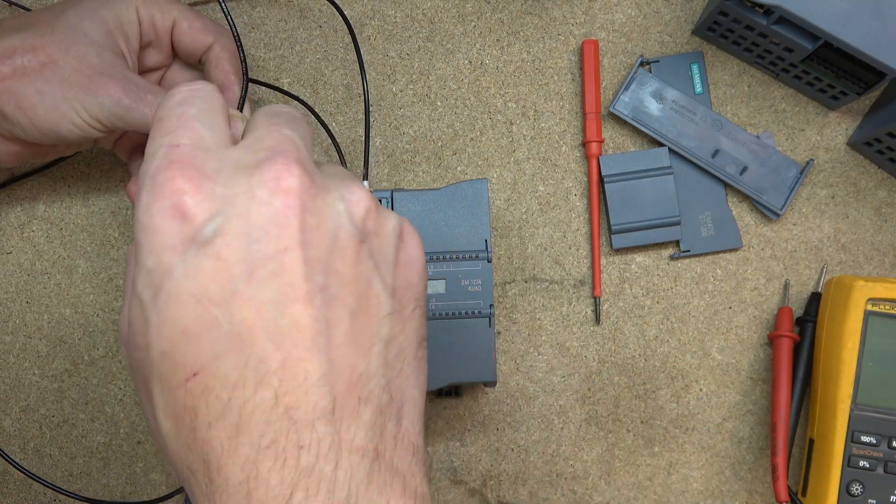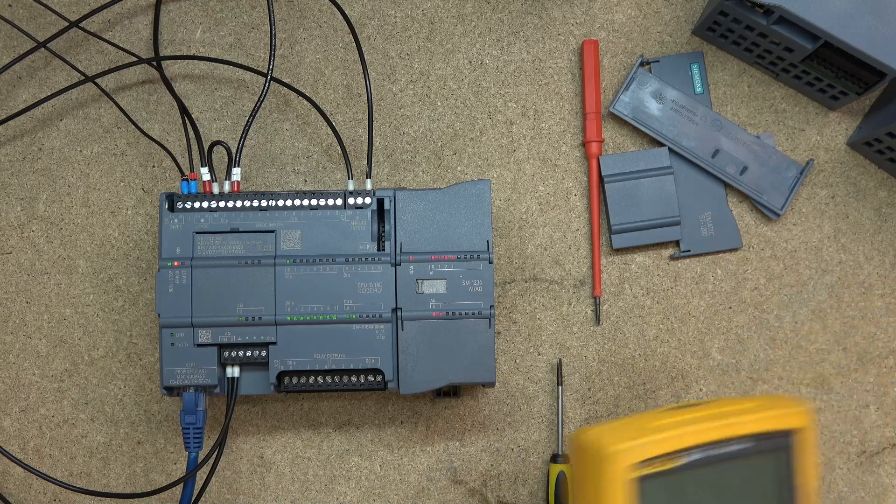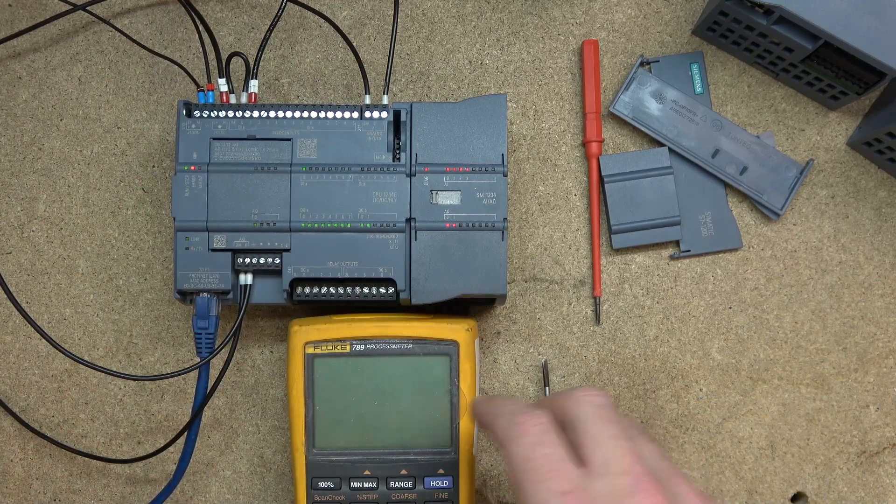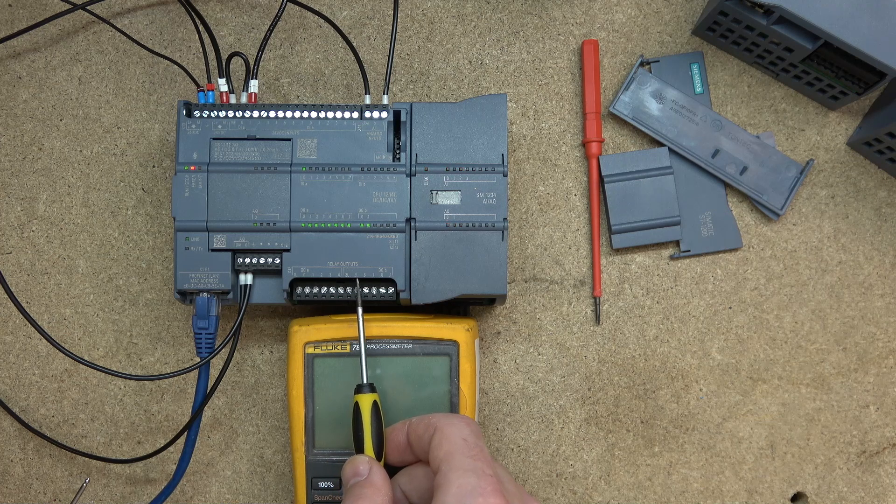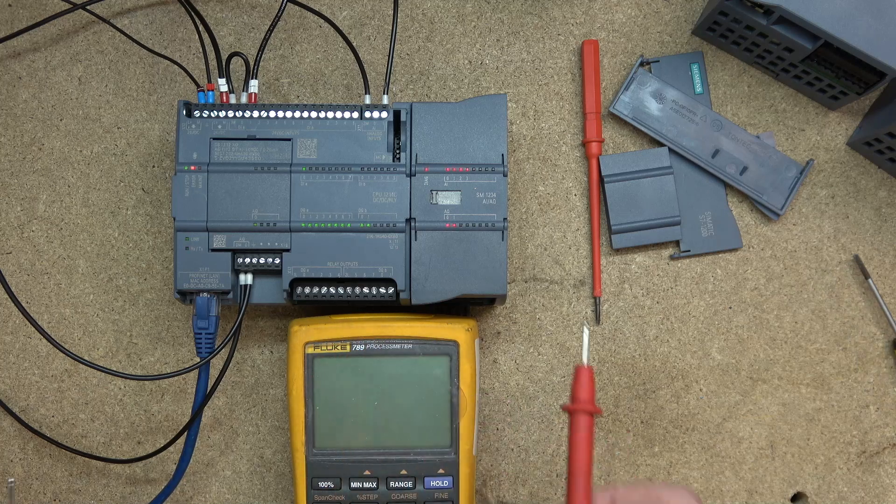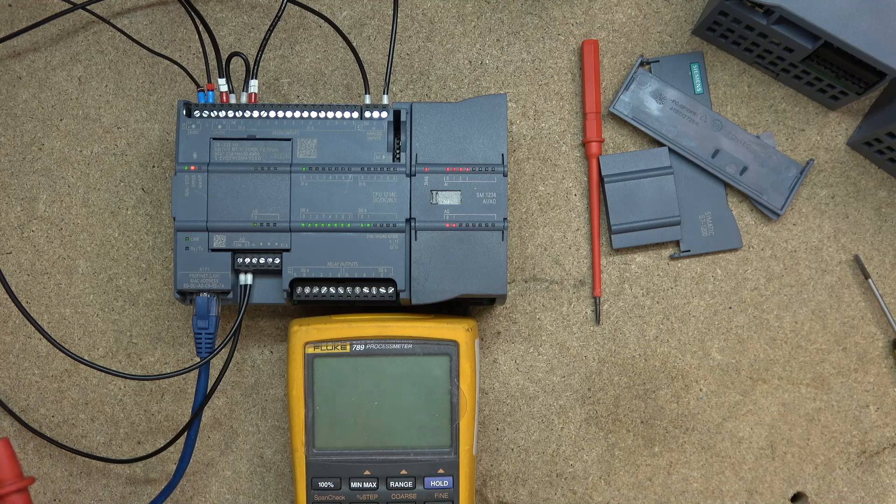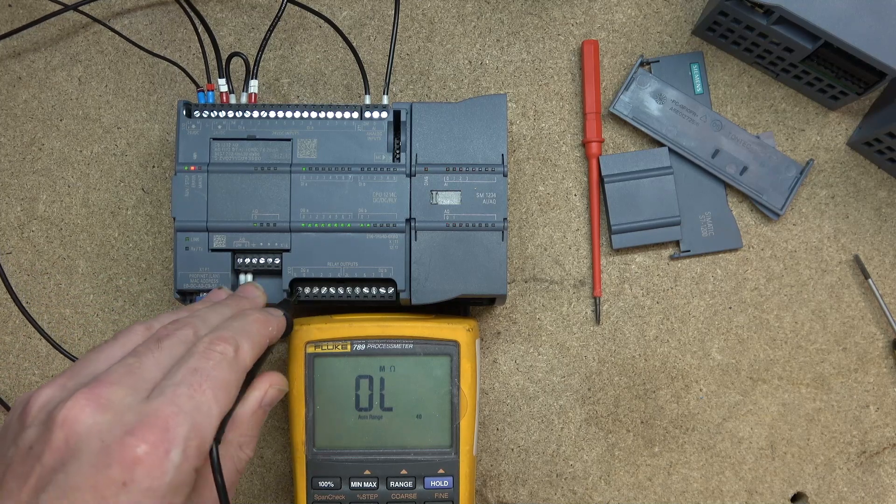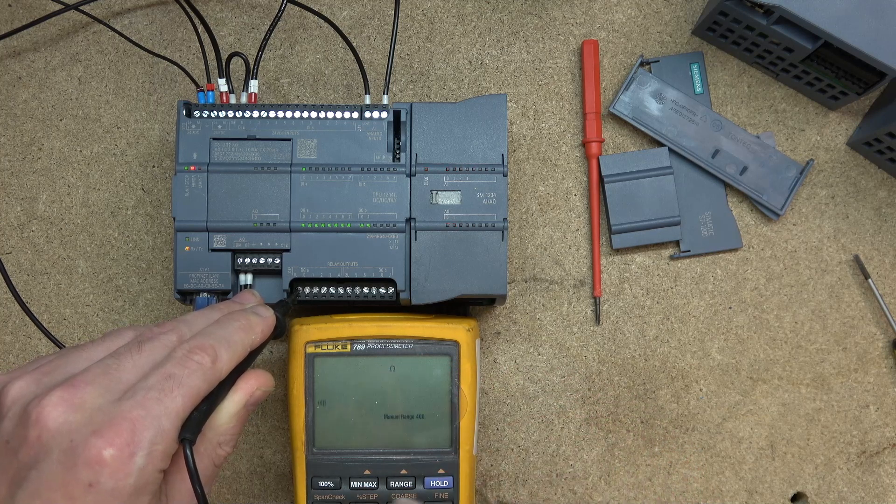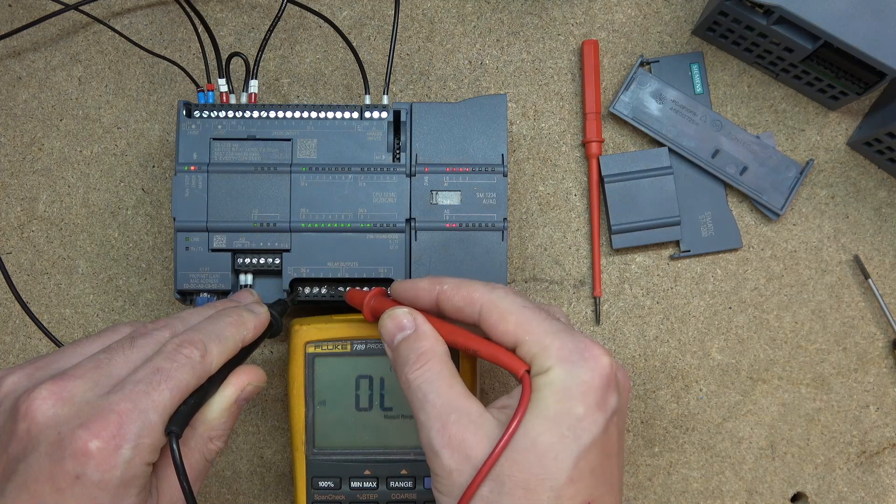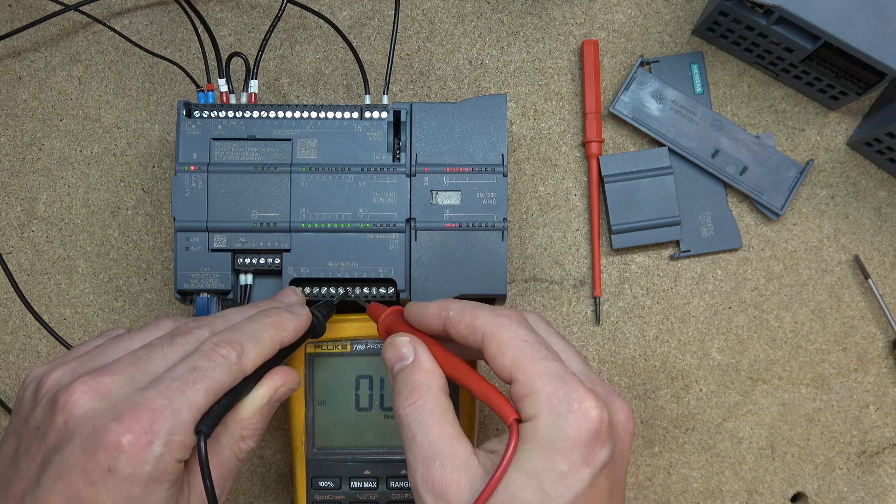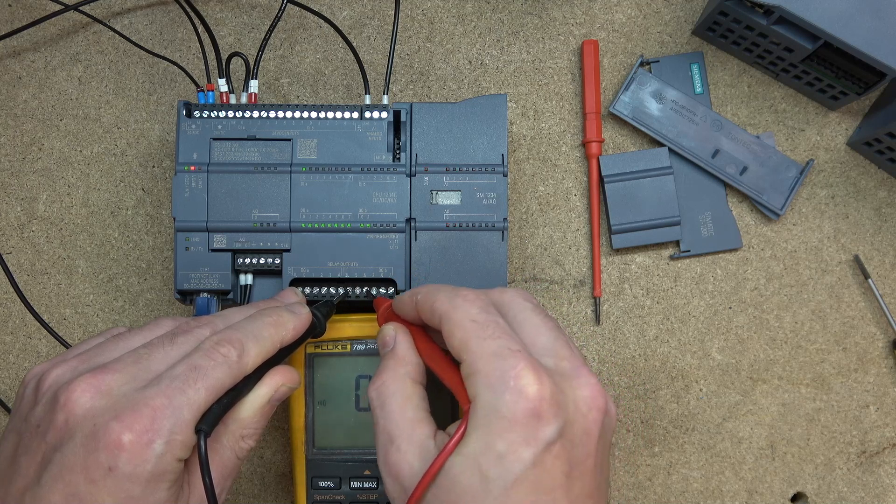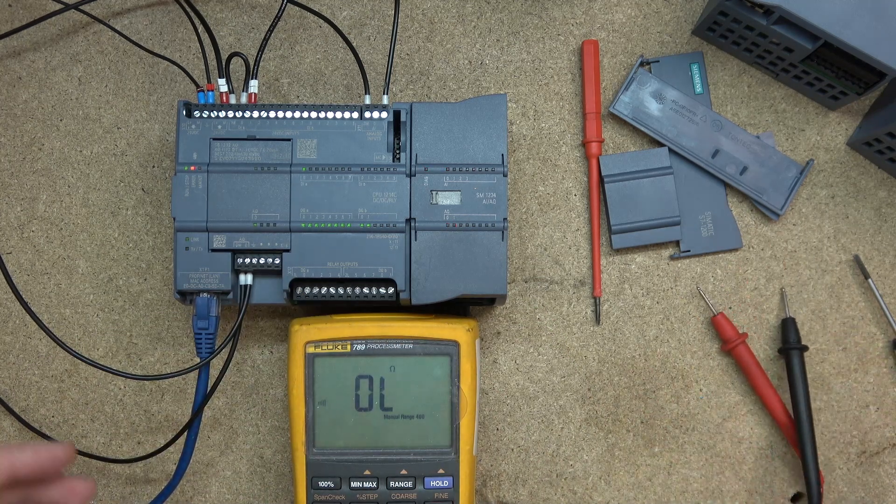Next we're going to do, as you can see, I'm going to put the cable in here and it closed off all my relays in here. What we're going to do is we're going to use our multimeter because it's relay output and it's got two sections. We've got L1 and L2. So L1 is going to be common for all of these, all the way to four and L2 is going to be common for five, six, seven, eight, or five, six, seven, eight, zero and one, whatever that is down there. Yeah. So let's put it in resistance mode. So we put one meter on our common, which technically if the relay is on, there should be a beep. Let's put the beep on it. So as the relays would normally work, that's working beeping. I'm not sure you can hear the beep, but it's beeping, beeping, beeping. The next one that we need to move into the, remember, this is the next section of the common.